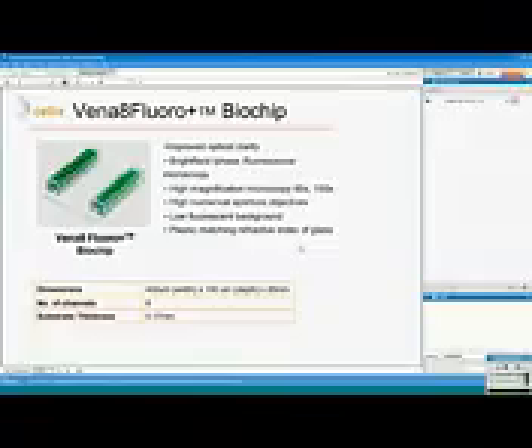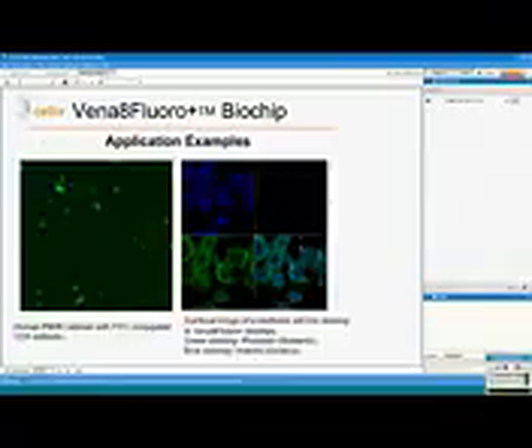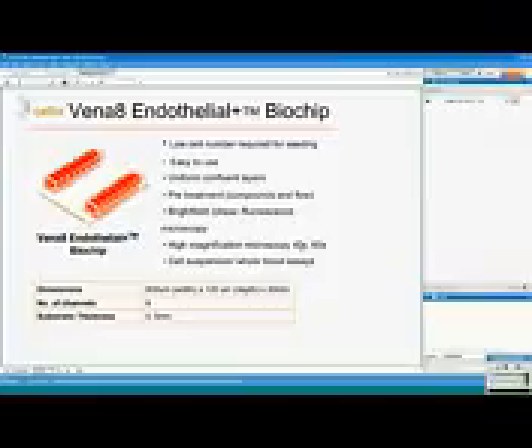If it is necessary to use fluorescent microscopy and to have a low fluorescent background, we recommend the Vena 8 Fluoro Plus biochip. It has improved optical clarity and can be used with high numerical aperture objectives, high magnification up to 60x and 100x oil immersion, bright field, phase contrast and fluorescent microscopy. It also has a plastic which matches the refractive index of glass very closely, so it can be used with confocal microscopy. Application examples are low-level receptor staining of leukocytes and other cells, and also confocal imaging of different cells. In this example, you can see confocal images of endothelial cells stained with different dyes.